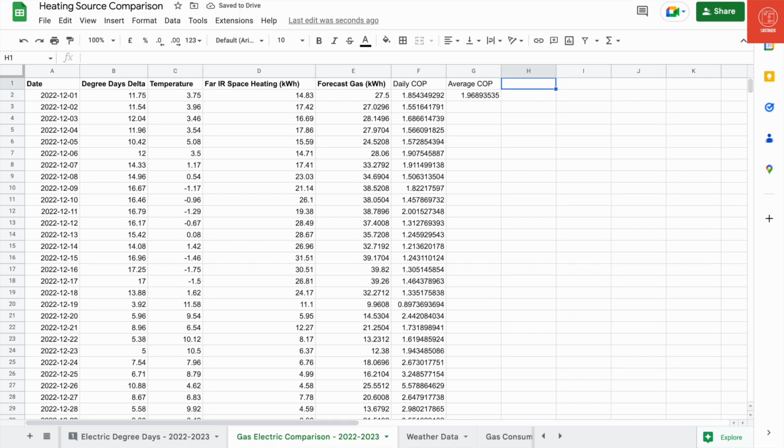There are several reasons for this. One of them is just the fact that we're using a combustible fuel like gas, so we will never get 100% of the energy within that fuel out of it when we burn it. As it happens, the boiler we were using was a 5-year-old Worcester Bosch condensing boiler. We were running at a very low flow rate, so we should have been achieving fairly high efficiencies, with the return temperature at 50 degrees or quite often under. So we should have been achieving decent efficiencies, but we won't have been at 100%, so that'll be part of it.